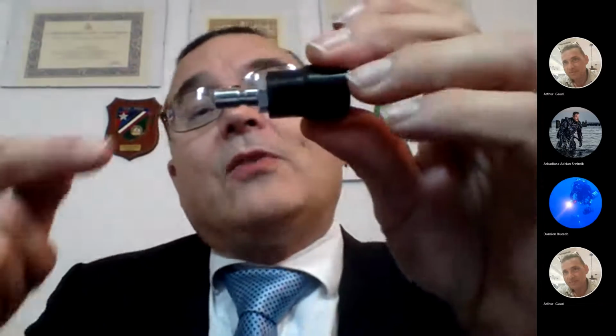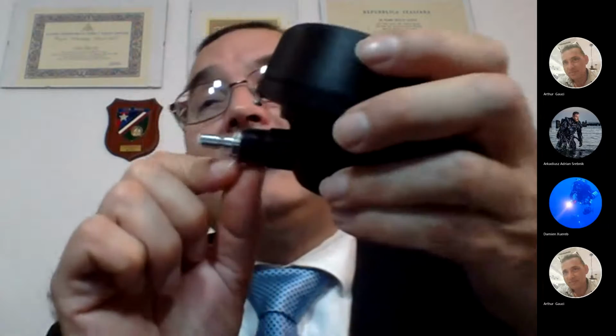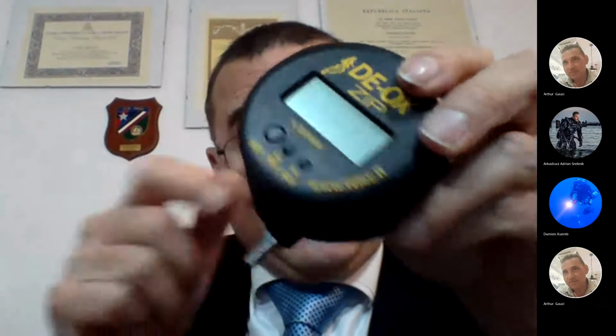Another way is using the flow restrictor from the BC hose, from the jacket. You just have to remove the adapter from the sensor, and then you just screw it on to the analyzer. In this way, you just connect the analyzer to the cylinder. Inside here there is a nut, there is a spring, and it's already calibrated for the constant flow that is around 1 liter per minute. In this way you provide the best flow, at constant temperature and constant pressure, to the sensor.